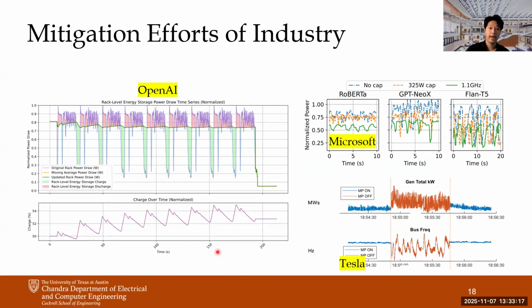In the case of OpenAI, they also consider rack level devices, using the energy storage system at the rack level. As you can see from this left figure, they can almost minimize the fluctuations by using rack level energy storage systems. But another point OpenAI has discussed is that for the rack level energy storage system, it is very difficult to minimize this ramping effect from the data centers. So the fluctuation of the data centers is a large problem in the grid, but this ramping behavior, which arises at the start or end of the training process, is also another large problem in the grid.